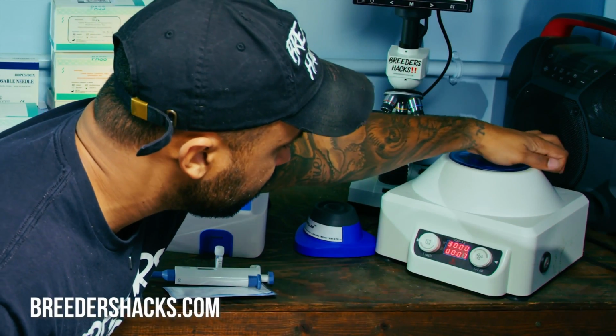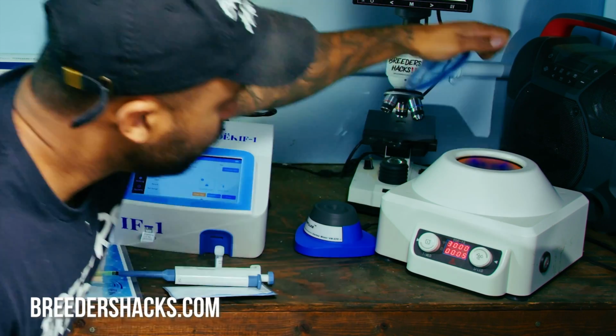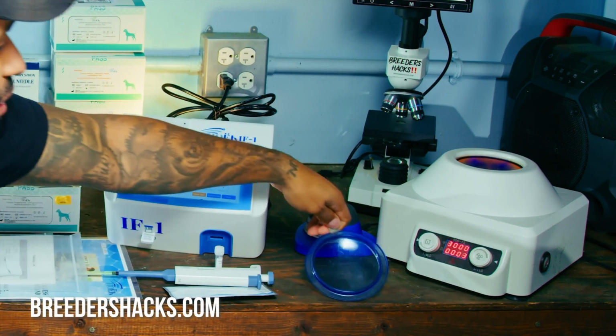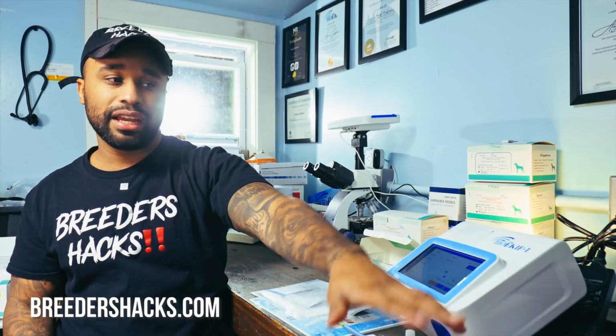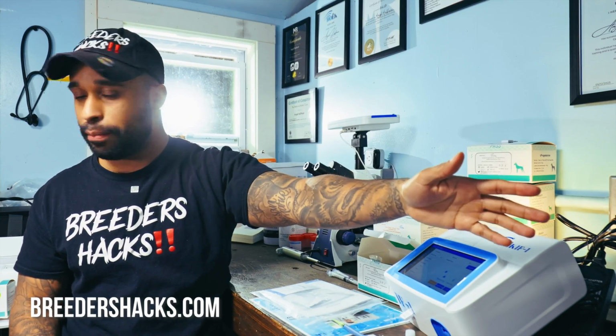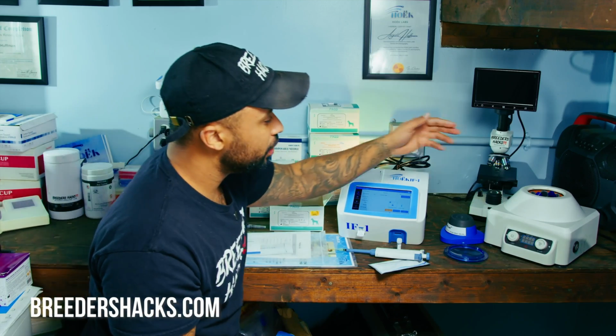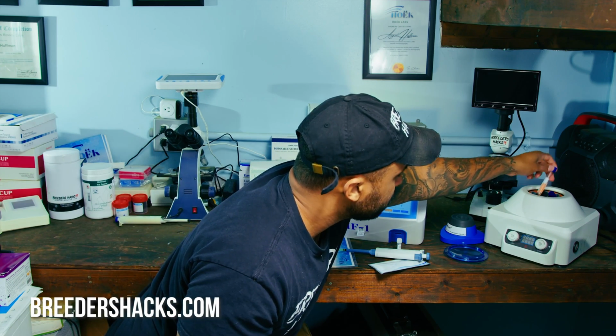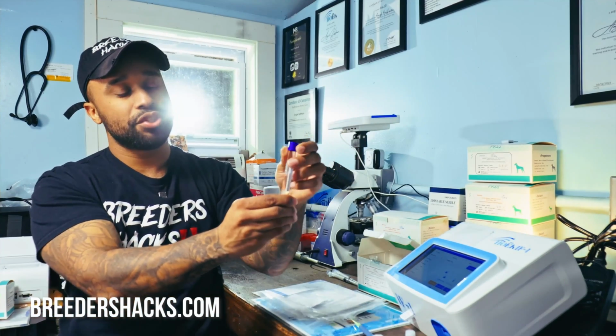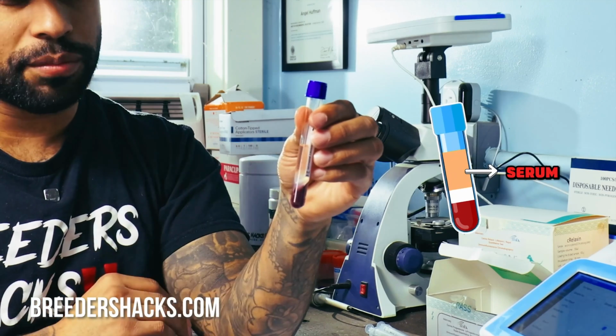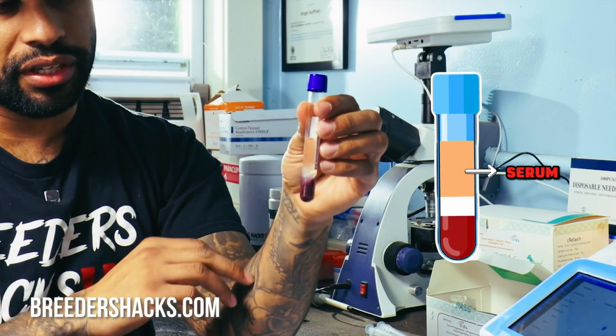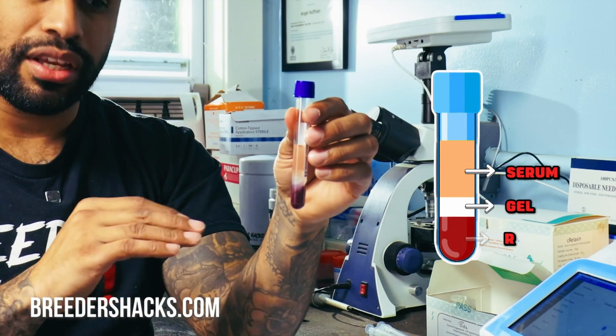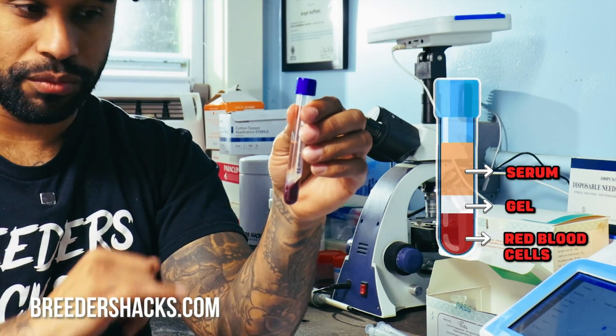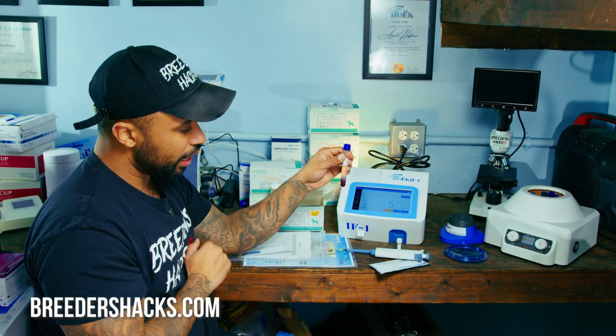All right guys, so our machine has been spinning, and as you can see, look how fast that is. We got about a couple of seconds, so it's going to shut off and stop on its own. Once our timer's up and our machine is done spinning for about 5 minutes, this is exactly what you want, guys. You want the serum up top that you can see, that's a liquid. Then we have our gel in between, and we have our red blood cells at the bottom. We're going to be testing with the serum up top.